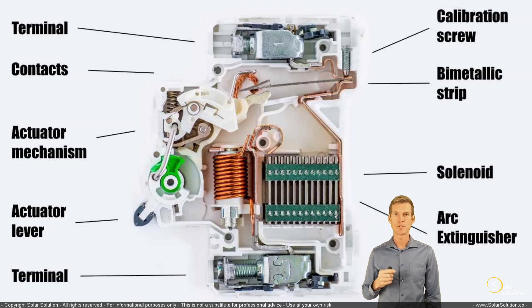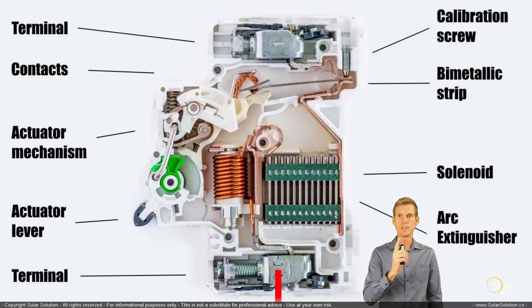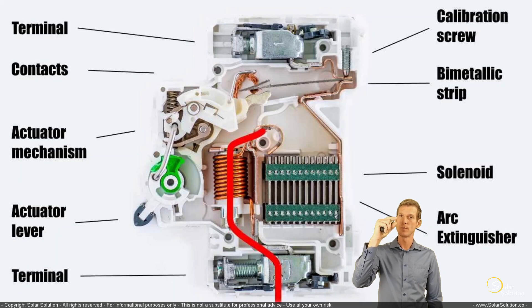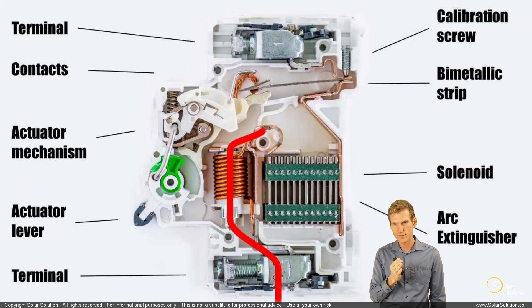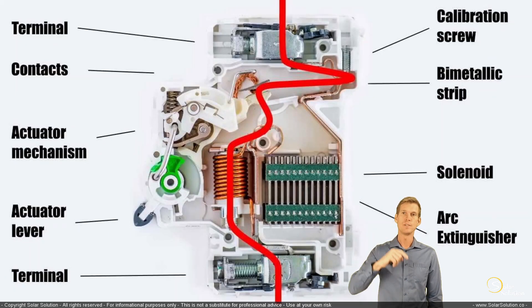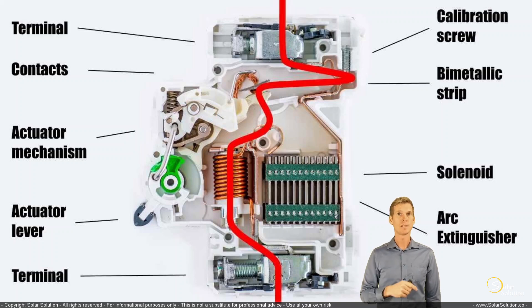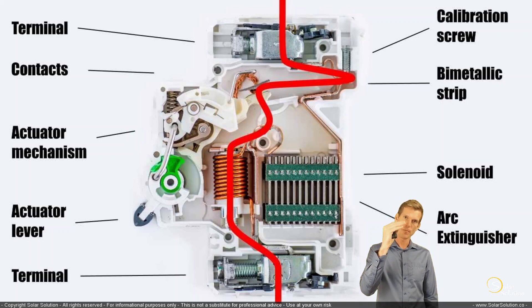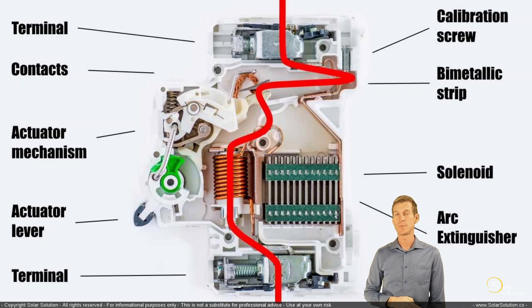Let's run through a current flow scenario. Current arrives at the bottom terminal, travels up through the solenoid, and when contacts are closed, runs through the bottom contact toward the top contact, then through the bimetallic strip and out through the top terminal. So all current passes through both the solenoid and the bimetallic strip. If the current is slightly elevated within the slow tripping region, the bimetallic strip heats up, bends, and pops the contacts open.